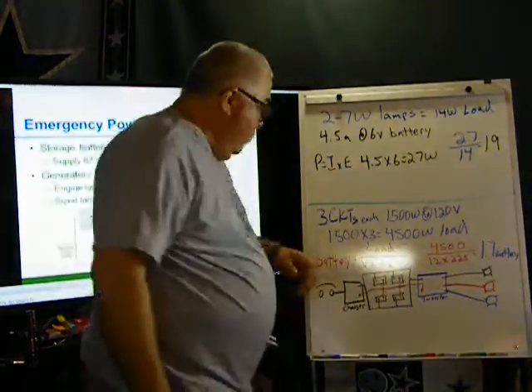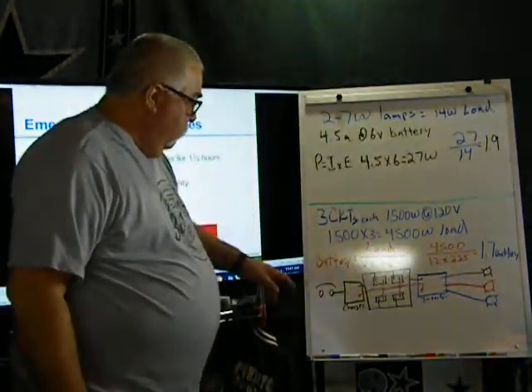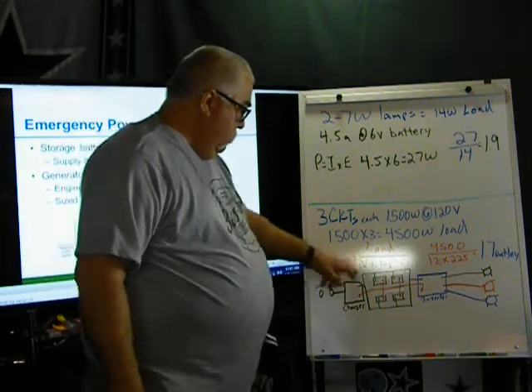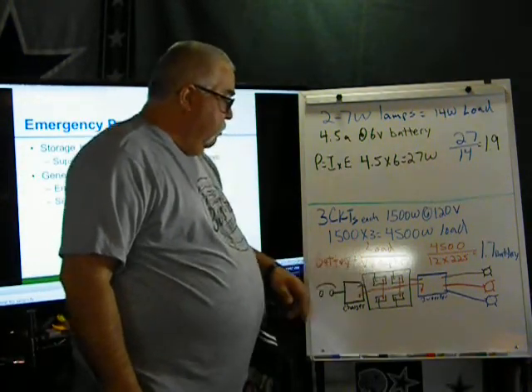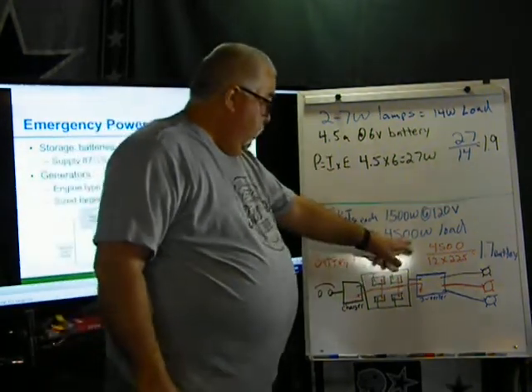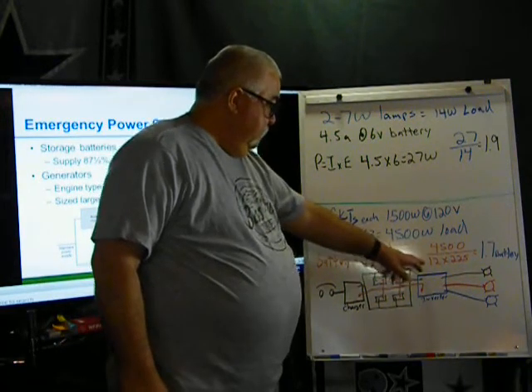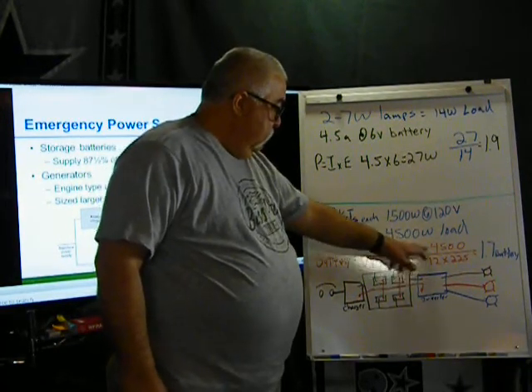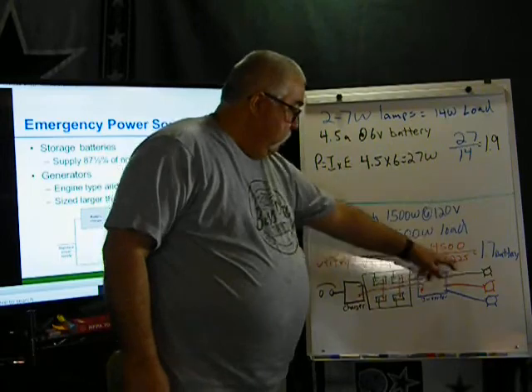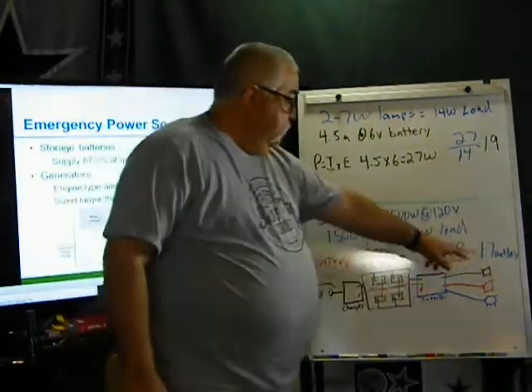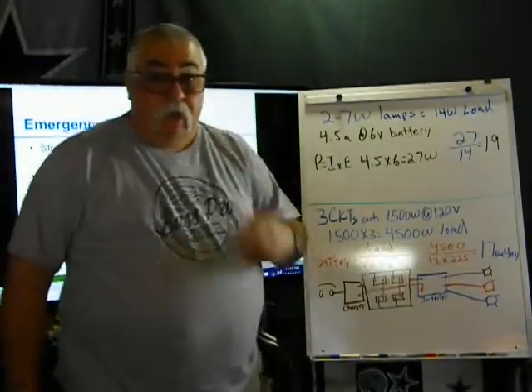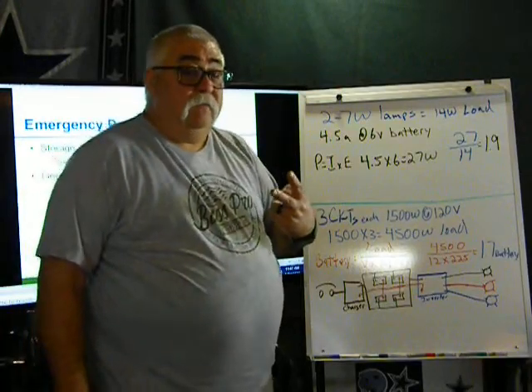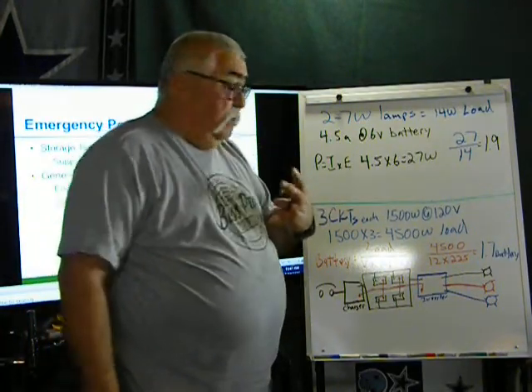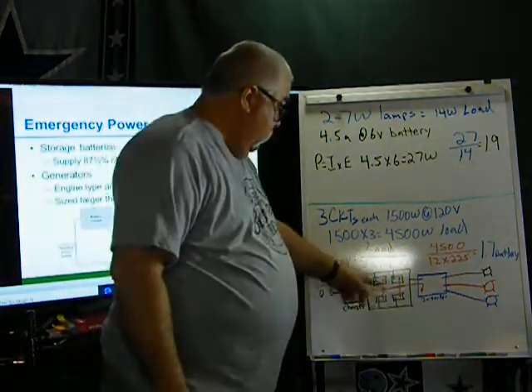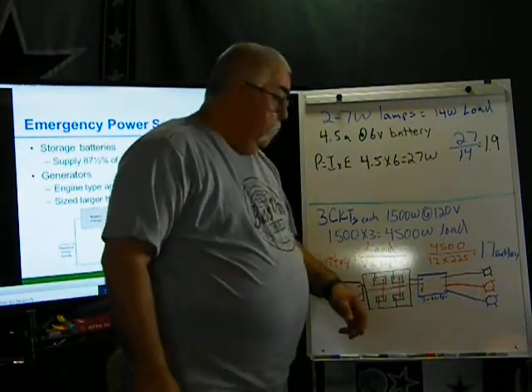So I'm using a 225 amp-hour battery. So batteries equals the load divided by the voltage times the amp hour. And it gives me the batteries. So I've got a 4500 watt load. 4500 divided by 12 times 225. They give me 1.7. So I need at least 2 batteries at a 12 volt system, so they would be in parallel. Okay, these are all in parallel.